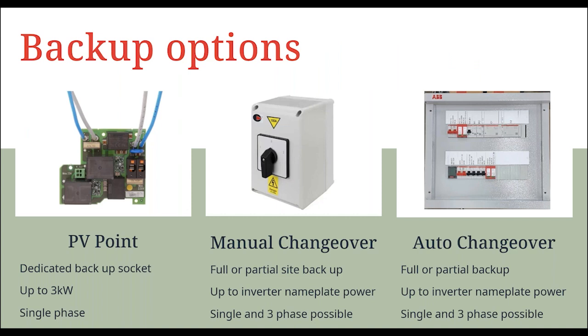Next is looking at some of our backup options that are now available. So we have already built into all of the Gen24s the PV point circuit. We have something new called PV point comfort, and we'll go into a little bit more detail with that shortly. We have manual changeover, so we can use an off-the-shelf changeover switch, and we can use that to isolate the house in an island mode. And we now also have the first batch of auto changeover units received into Fronius UK. So let's have a look at each of these three in a little bit more detail.